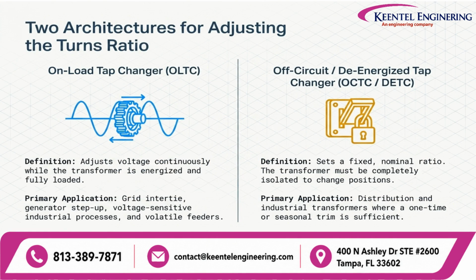Transformer tap changers are broadly divided into two categories: on-load tap changers, or OLTCs, and off-circuit or de-energized tap changers, commonly called DETCs. An OLTC can change transformer taps while the transformer remains energized and carrying load. This makes it ideal for transmission substations, renewable integration, and industrial facilities where continuous voltage regulation is required. In contrast, a DETC can only be operated after the transformer has been completely de-energized. Because switching requires an outage, DETCs are typically used where voltage adjustments are infrequent, such as seasonal network optimization or fixed distribution transformers. Selecting between these two technologies depends on operational flexibility, maintenance strategy, cost, and system requirements.